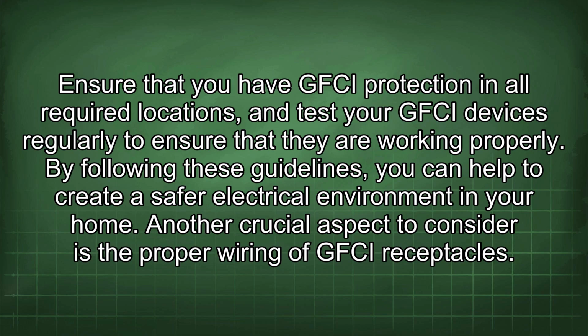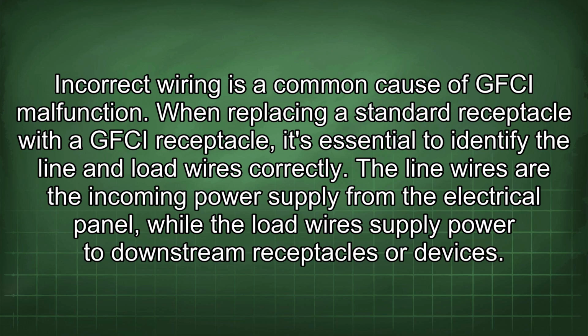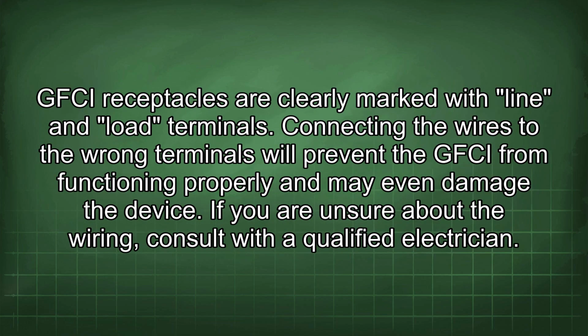Another crucial aspect to consider is the proper wiring of GFCI receptacles. Incorrect wiring is a common cause of GFCI malfunction. When replacing a standard receptacle with a GFCI receptacle, it's essential to identify the line and load wires correctly. The line wires are the incoming power supply from the electrical panel, while the load wires supply power to downstream receptacles or devices. GFCI receptacles are clearly marked with line and load terminals. Connecting the wires to the wrong terminals will prevent the GFCI from functioning properly and may even damage the device. If you are unsure about the wiring, consult with a qualified electrician.